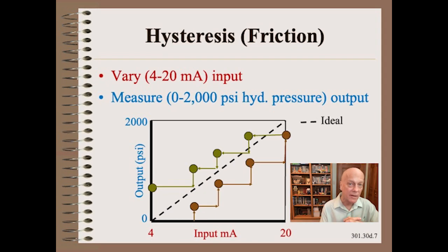Lack of repeatability, and particularly hysteresis, which is the offset of the load and unload curves, is not only common with elements that move, it is the norm. However, what is not normal here is that the deviation is quite noticeably large. So much so that the control curve is 3 to 5 steps, none of which will repeat on the next calibration.